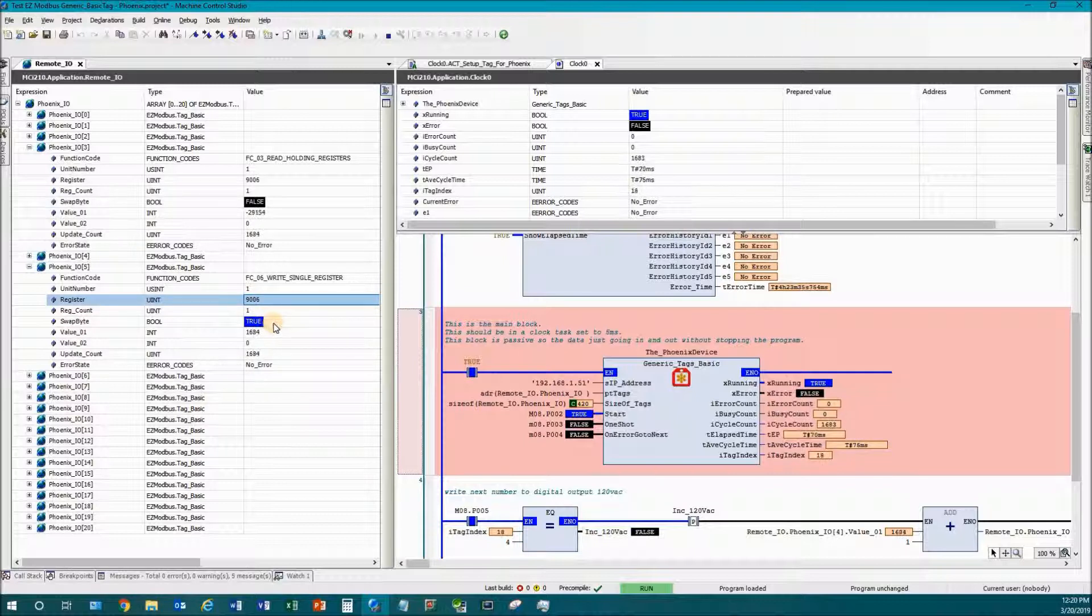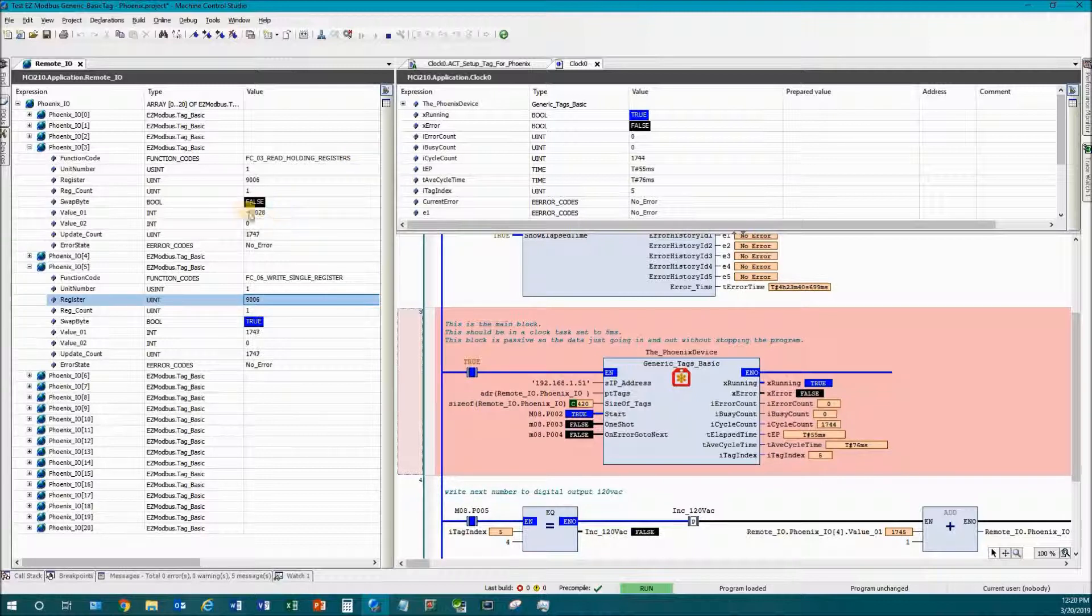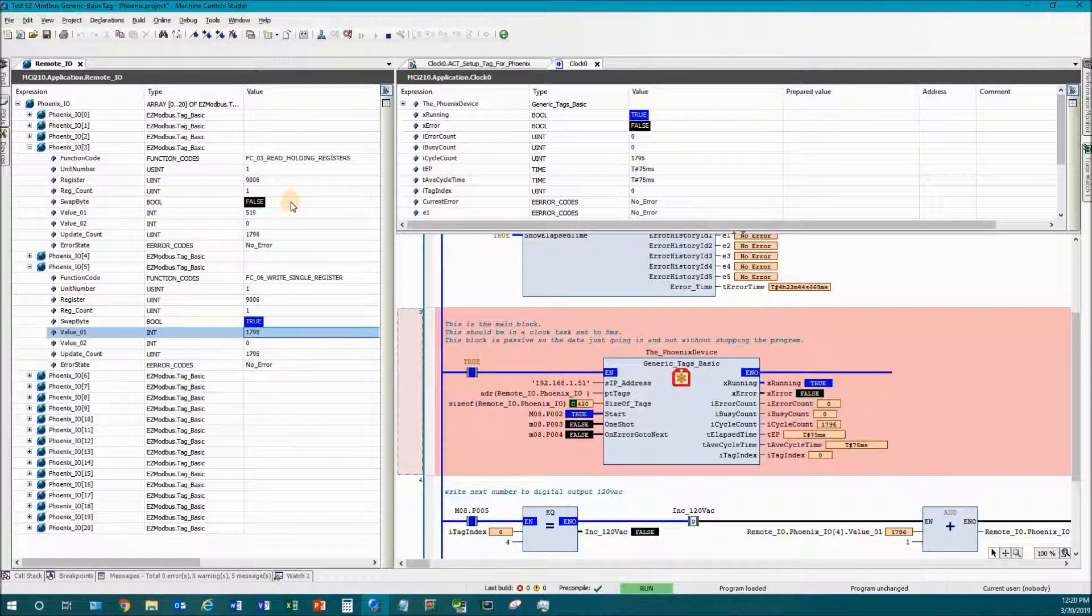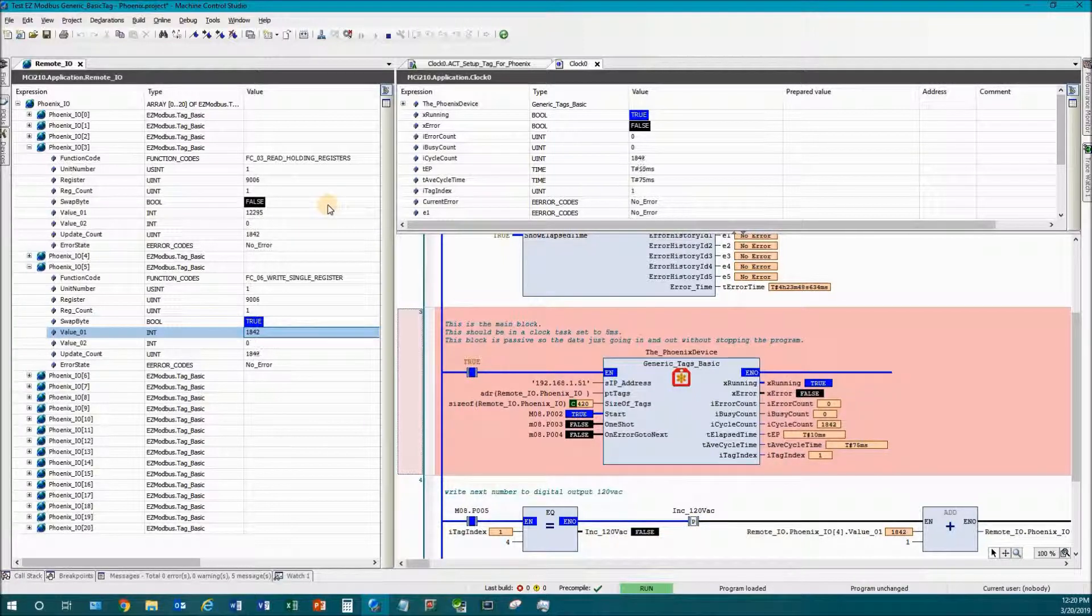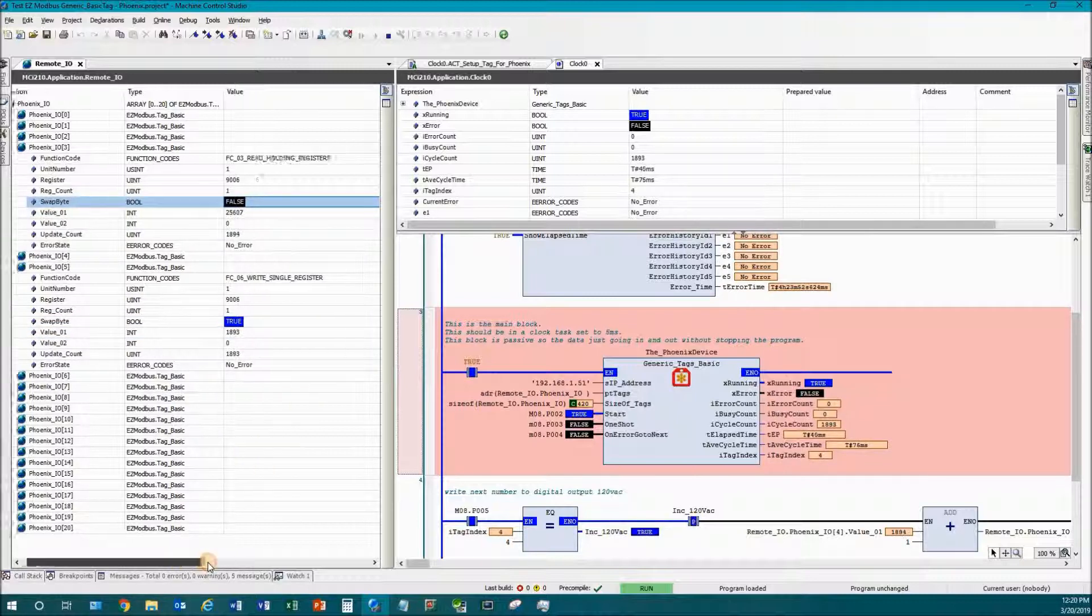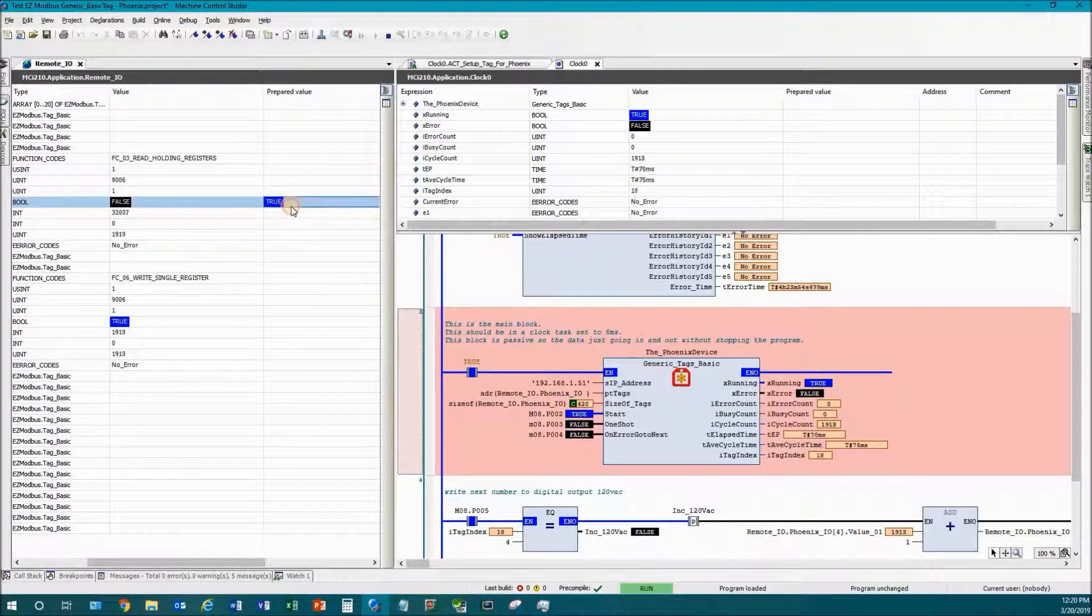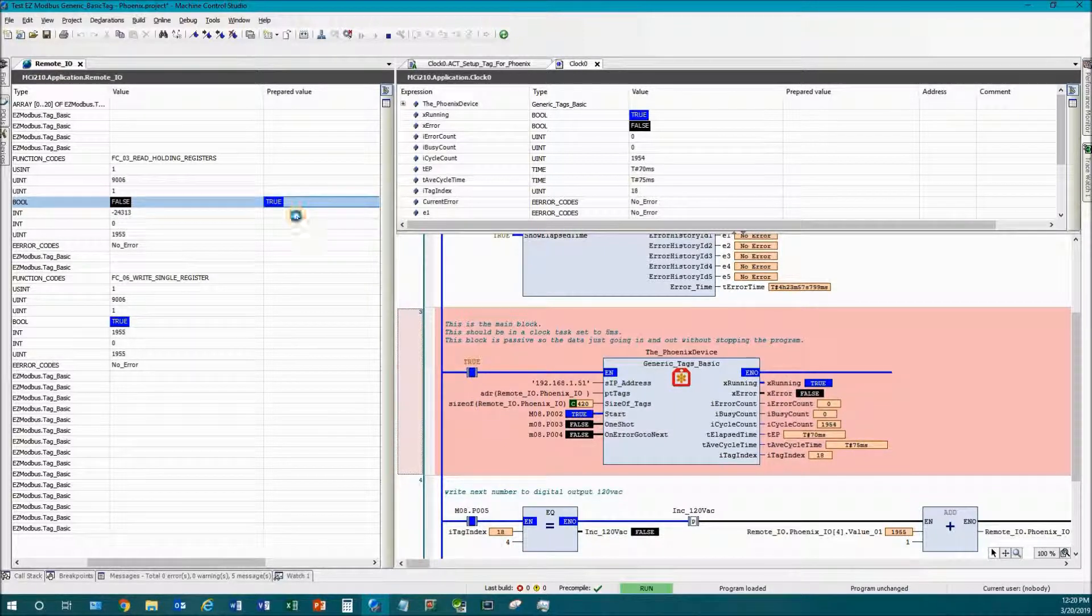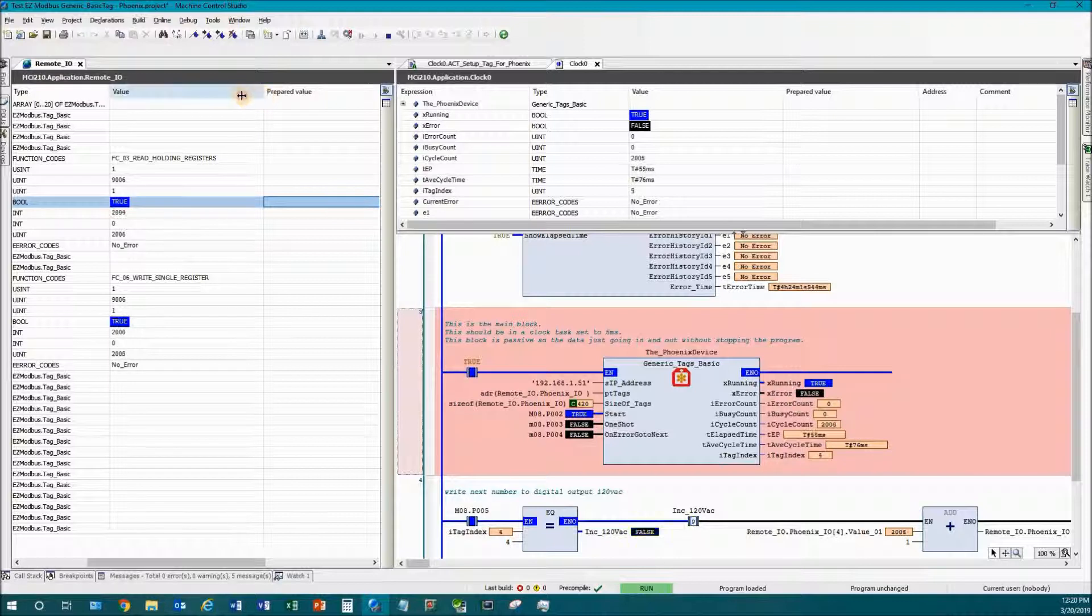Here's the same register so we're writing here and we are reading here. You notice that the data here isn't matching - that's because when I came back over here I forgot to turn on the swap byte we just got done talking about. So I'm going to force it on. Now that it's forced on you can see that the data lines up.